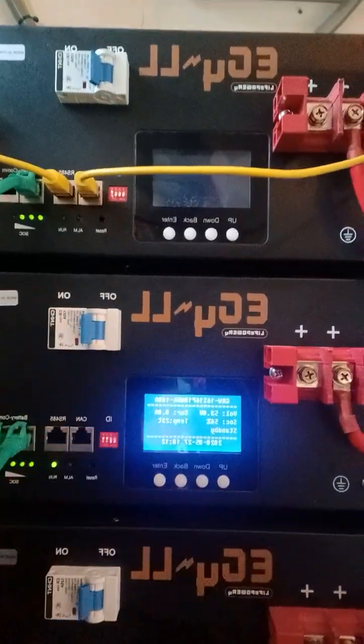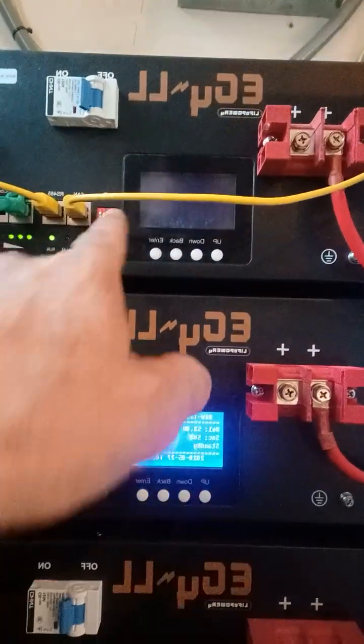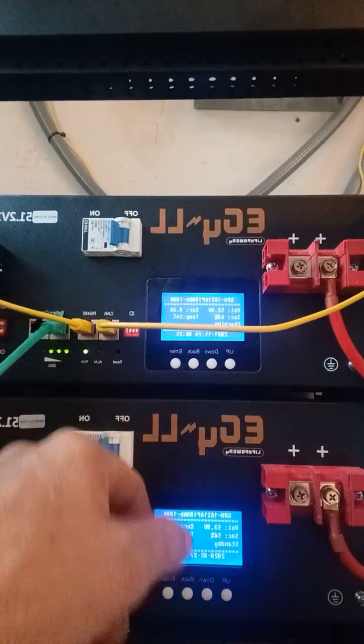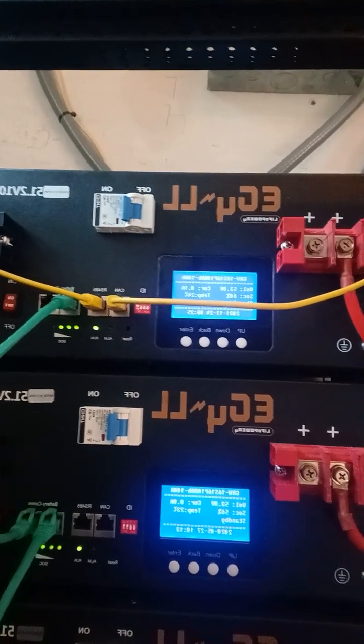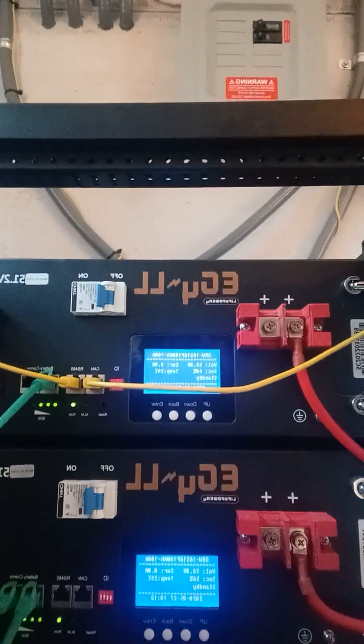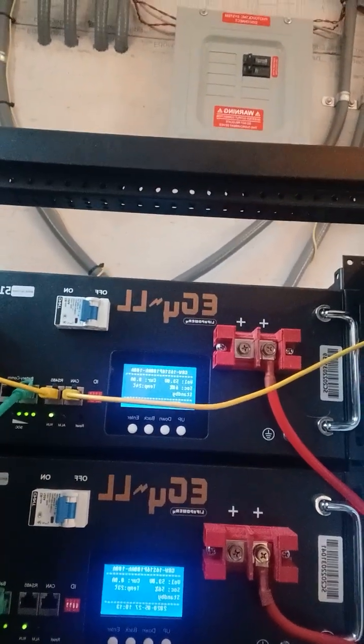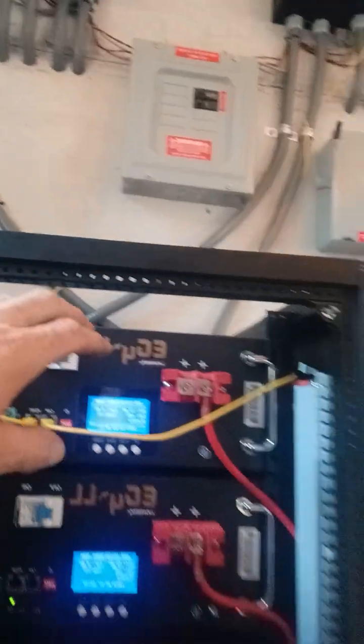The BMS is showing that the battery's about 56% right now. They are charging at one to two amps. A lot of sun production today, and now it's pretty much at the end of it, so they are pretty much topped off for this afternoon. I've got 60 on one, 56 on another, 57 on the third. There's a little bit of a difference because we were testing — there's about 5% more battery life on this one simply because we were only turning it on in the beginning.